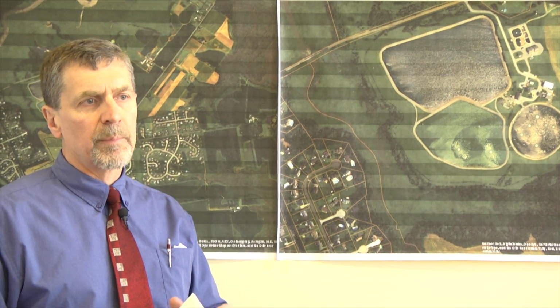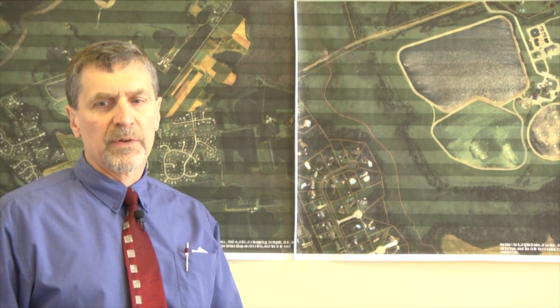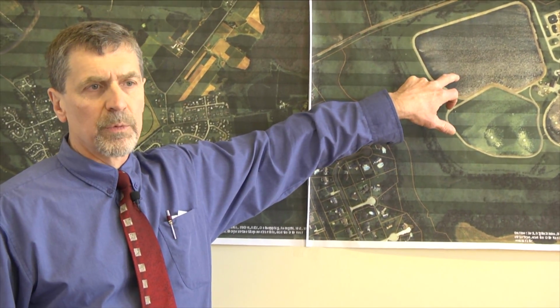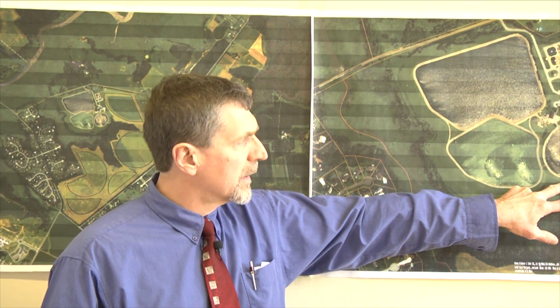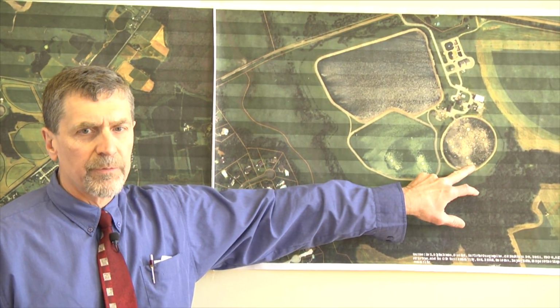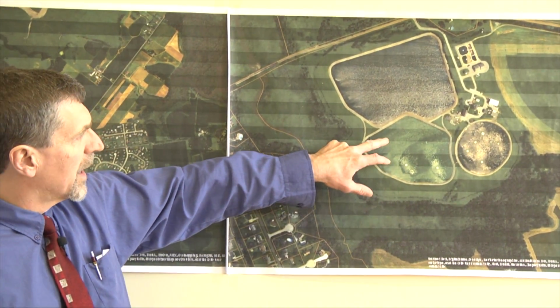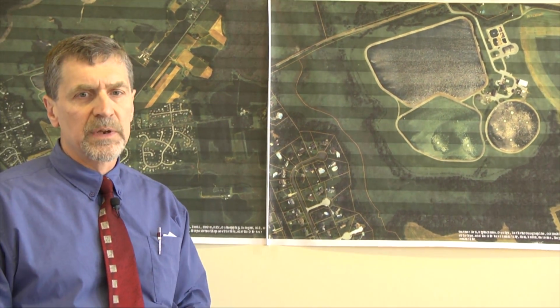You need a lot of time for that water to go through those lagoons, to have residence time in those lagoons for the biological activity, to get to a finished effluent product which is suitable for discharge or irrigation. As an example, this treatment plant was designed so that from the time a drop of water enters that first lagoon, it's between 35 and 40 days before it gets to our final lagoon, and that's basically the time you need to treat that water.